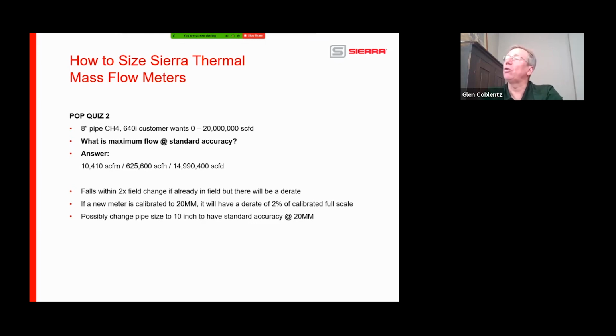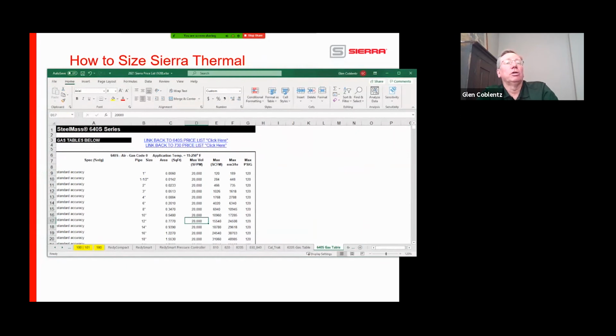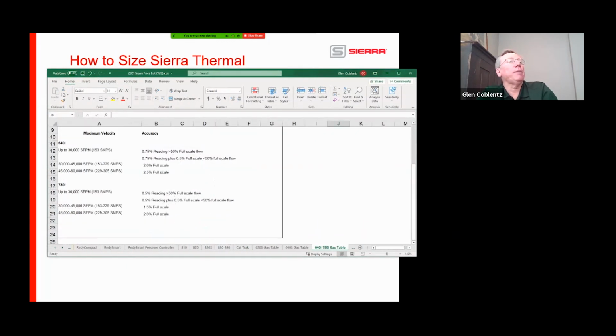I'd call it, we probably go to 1, maybe 2% of full scale accuracy, but they're not pulling it out of the line. They don't have to shut down anything. They're up and running. Okay. If this is a brand new meter and it's calibrated to 20 million, it will have a derate, 2% of calibrated full scale. Because if you remember, we go back to the price list, we do have that option.